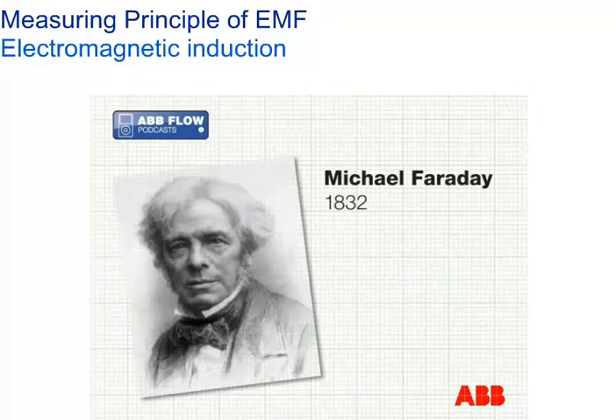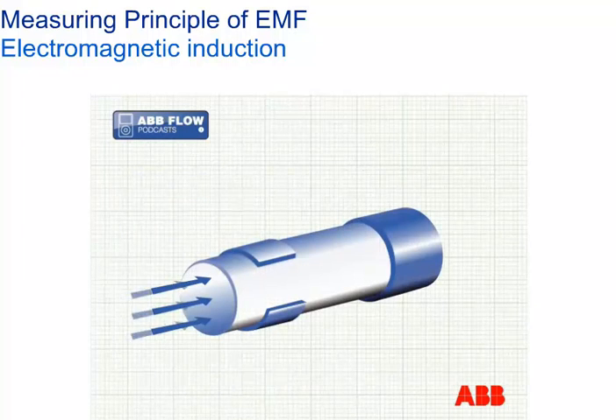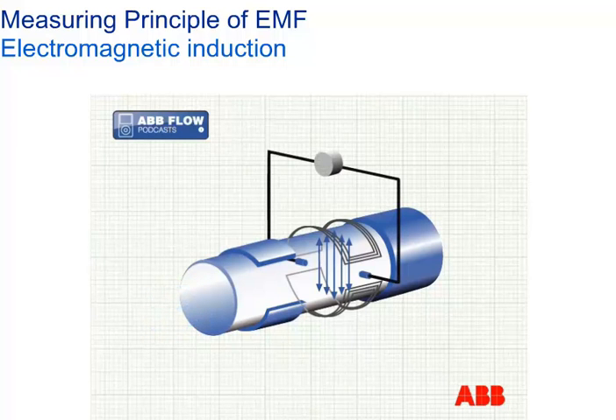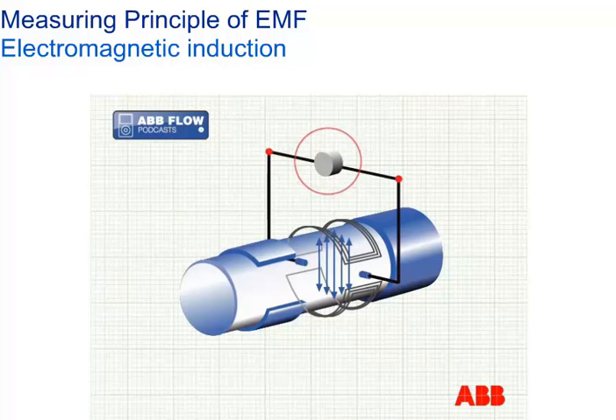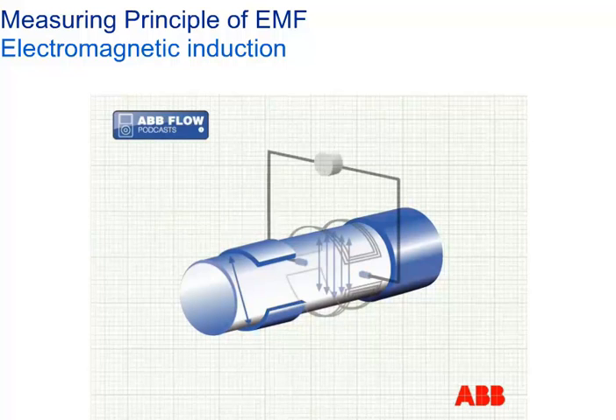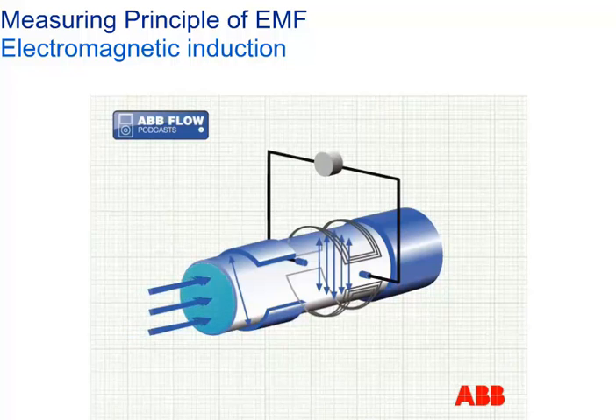Electromagnetic flow metering is based on the principles of Michael Faraday's 1832 discovery. When a conductive liquid, such as water, is moved through a magnetic field, a voltage is induced in the liquid at right angles to the magnetic field. The size of the voltage is directly proportional to the volume flow rate. This induced voltage is detected by sensors known as electrodes, which transfer the voltage signal to the processing electronics where it can be converted into a usable industrial standard signal. It is important that the flow meter tube is non-magnetic — austenitic stainless steel is the most commonly used material.